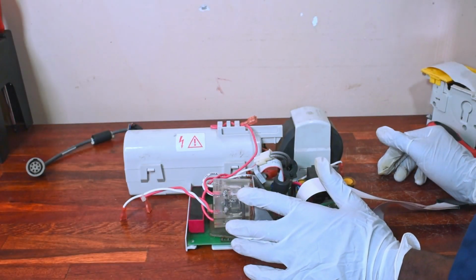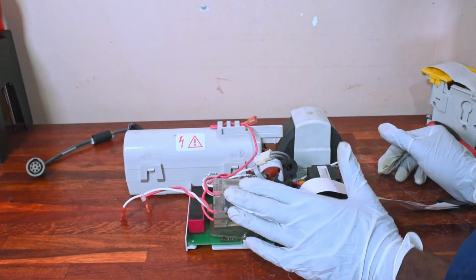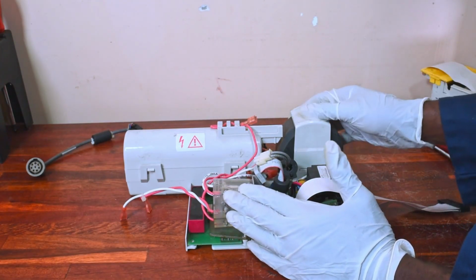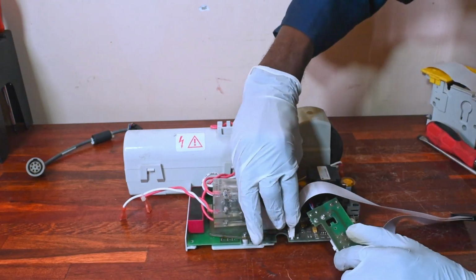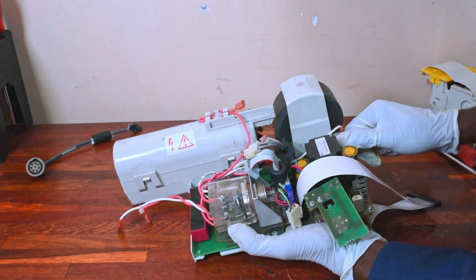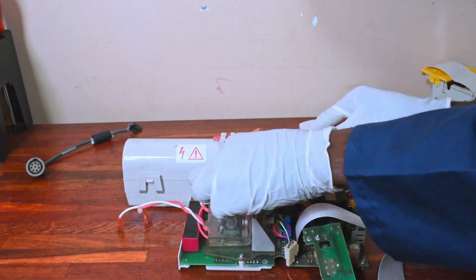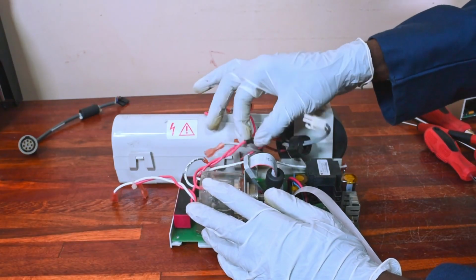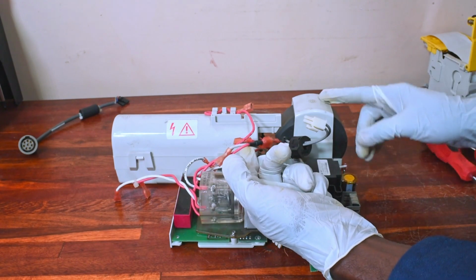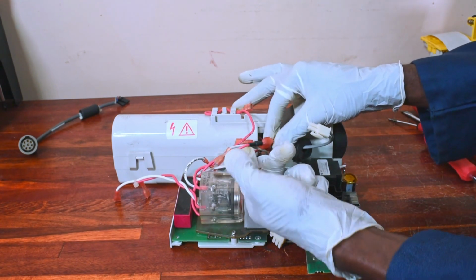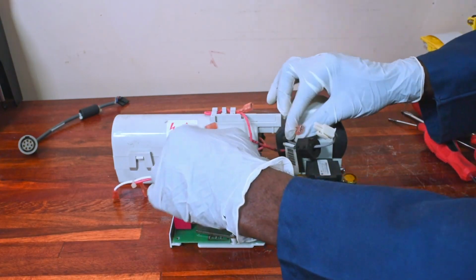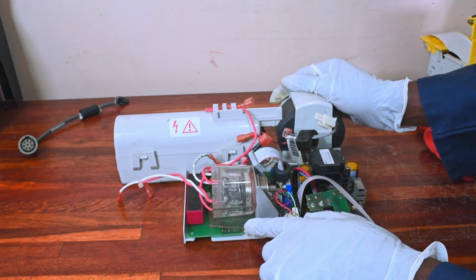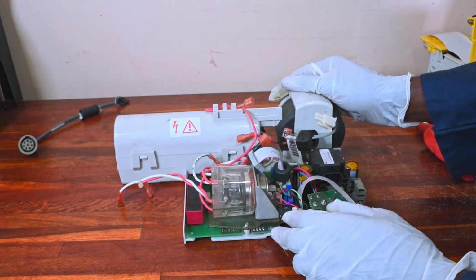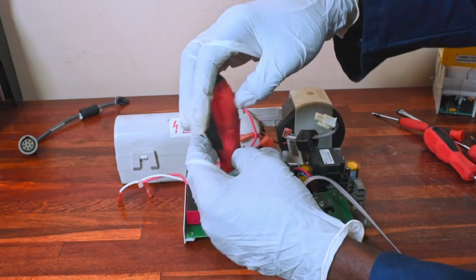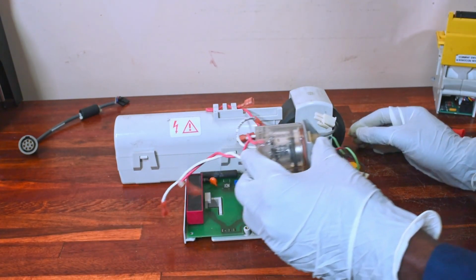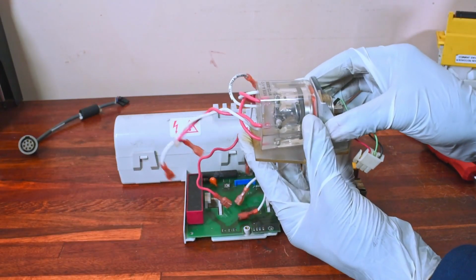To remove the patient relay, we have to disconnect the wires running between the patient relay and the high voltage capacitor, the patient inductor, and the control board. There is also one wire that runs between the patient relay and the patient inductor. So you need to disconnect the two wires. After doing that, I will remove the single screw that supports the patient relay to the high voltage control board. So this is the patient relay.